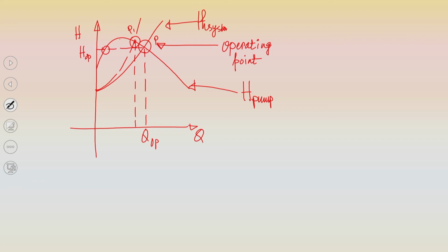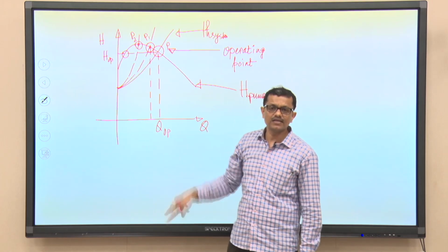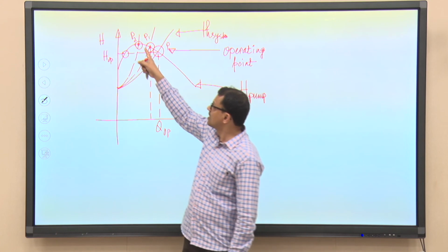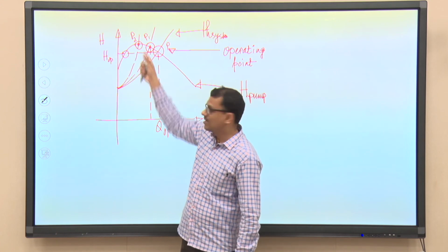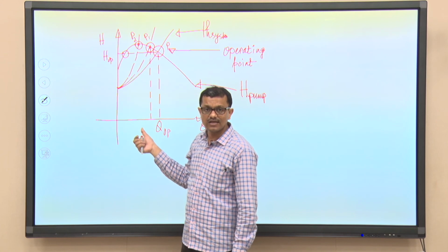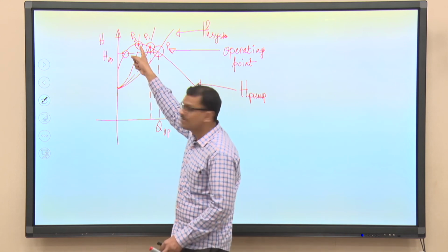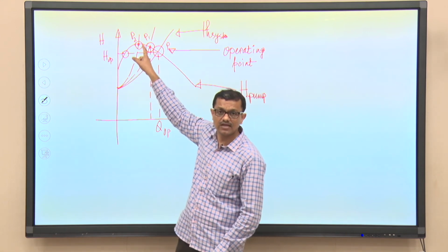So, this is P1, and in any case if the operator closes the valve further and the point comes over here, that is P2, right. So, this is P2, let me erase it. Now, when we are getting the operating point over here, of course, our objective is to have even lesser discharge from the pumping station. The consequence is that the operating point is now here, maybe we are getting less discharge, but the head that the pump is encountering is the maximum. So, maximum head.